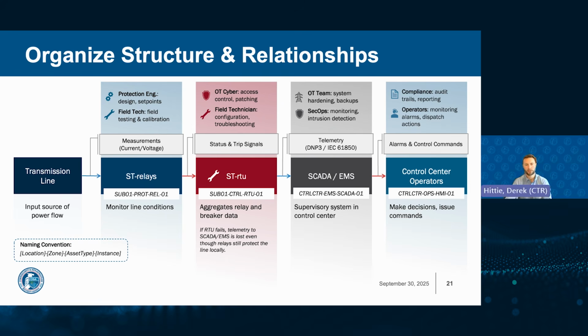Let's walk through a quick illustration we have on the screen, moving from left to right across the transmission environment. We start with the transmission line because this is the input source of power flow. So its condition, things like current, voltage, and frequency, become the raw data that every downstream device depends on. Next, we have the relays. Relays depend on current transformers and potential transformers to give them accurate electrical measurements, because without those measurements, they can't detect faults or issue trip commands. Their interaction here is to monitor line conditions and send trip or status signals downstream to the RTU.